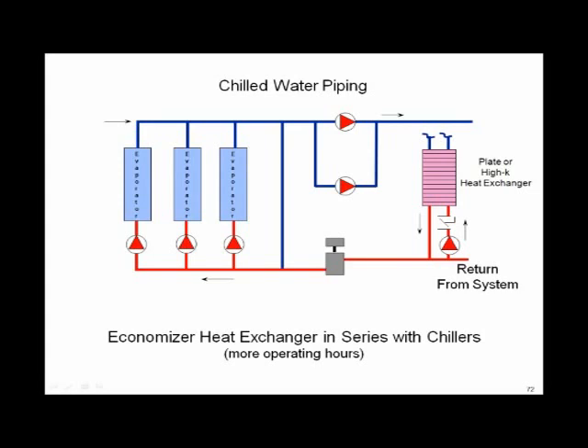Let's look at the chill water side of the water side economizer. What you want to do is get free cooling. You want to be able to provide chill water BTUs to the plant and save energy costs. That's what you're trying to make happen. If I'm going to integrate the water side economizer in with the chillers, where do I pipe it? And I think everybody's pretty well agreeing, there's only one spot left. It's not going to be in parallel with the chillers, it's going to be in series. So we're going to put it on the return chilled water side of the chiller plant.